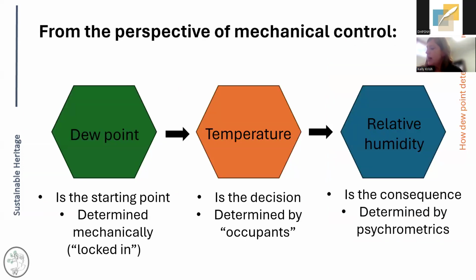Okay, so from the perspective of mechanical control, and this largely relates to summer conditions, the timing for this is perfect because I think it'll all be on our minds for the next 6 months or so. Essentially, dew point, again, is your starting point. Whatever your system is, whatever that cooling coil is designed to achieve, whatever that chilled water temperature is, that locks you into what possibilities you have.